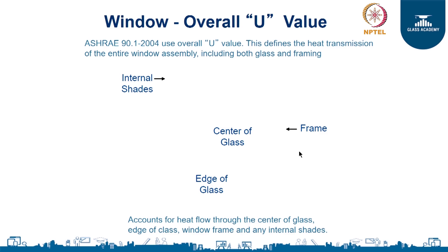When we look at the U-value, we typically look at the assembly of the envelope and not the individual component. For example, you will have glass and a frame around it, or some material around the glass to create an aesthetic effect or to fix the glass on the envelope. When we do the U-value calculation we take both materials together because it is the assembly which matters. Typically the assembly needs to be tested in a lab, and you get the U-value to use in simulations for a more accurate perspective on conductive heat transfer.